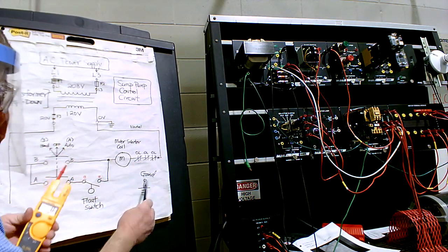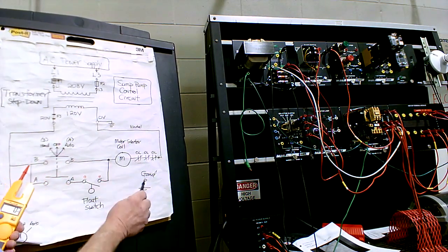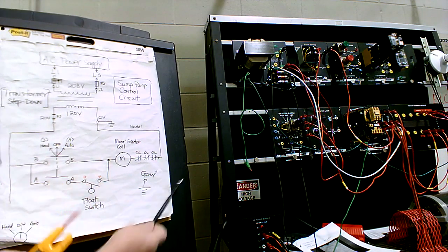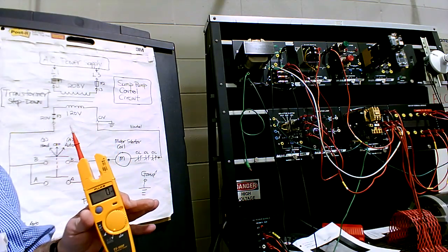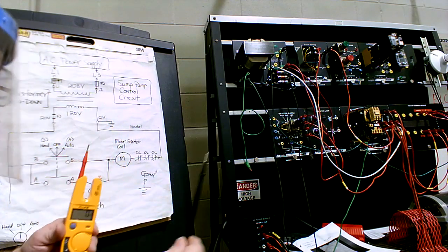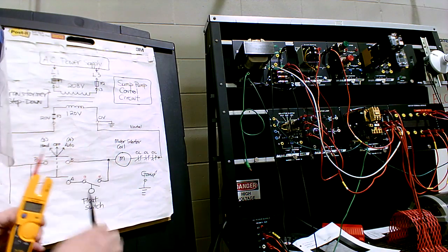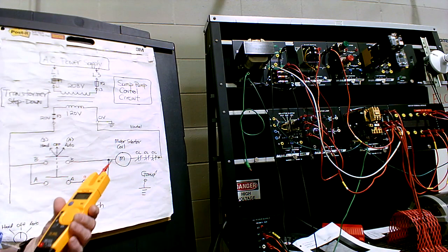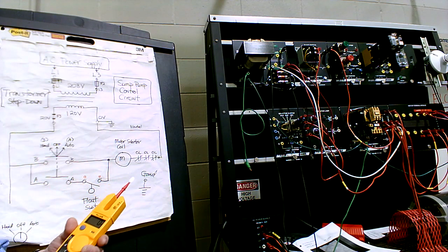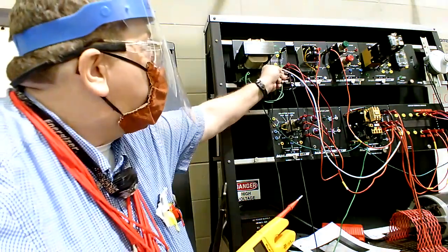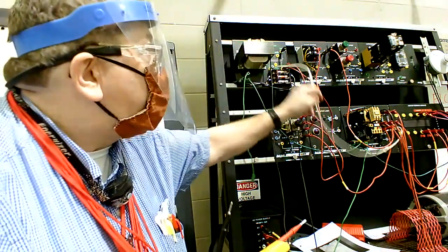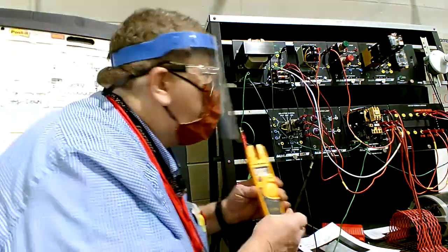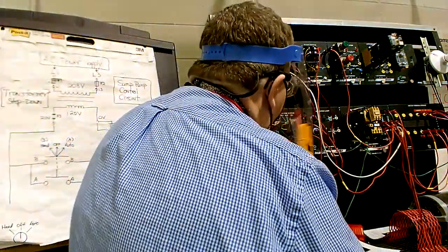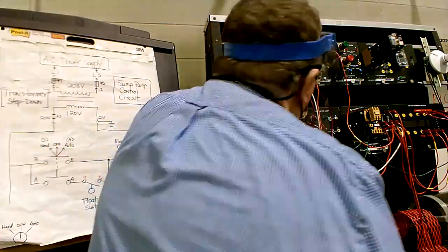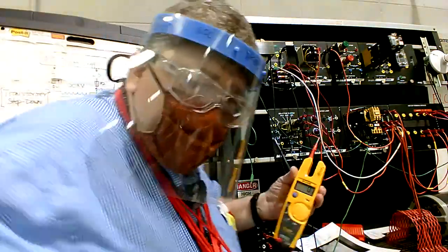You can't go to just any ground. If you go to some other grounding point other than neutral, you're going to get some bad readings, and we're just going to demonstrate that. And that's the whole point: for your reference on the meter, if you do not ground the secondary, if it's floating, and every now and then you hit a system that's that way, it's not very common. It's uncommon from my background. If you don't bond that neutral to ground, then neutral is the only valid point that you can use as a reference point. You've got to go to neutral like this. You got to go to neutral.